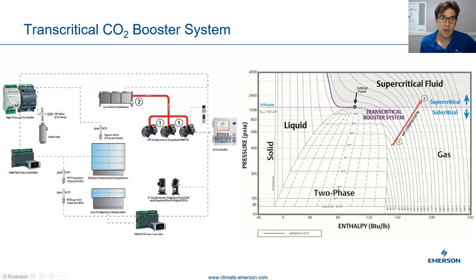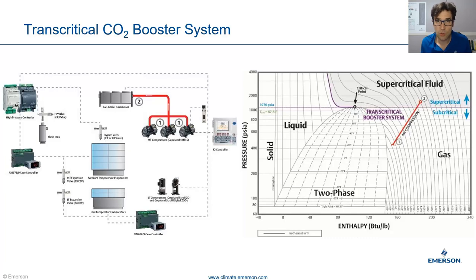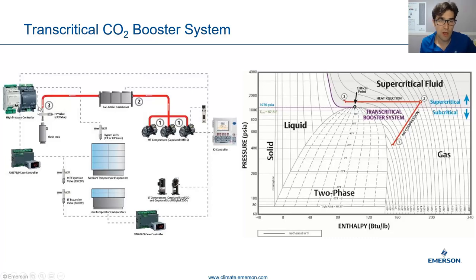From there we go into something we call our gas cooler condenser. We call it a gas cooler because when we're in that supercritical fluid zone or the transcritical zone, there's no pressure-temperature relationship, and we're just cooling the gas — we're not condensing. So as we go through there, we're rejecting the heat. We go into what we call our high-pressure valve, something very unique about CO2.